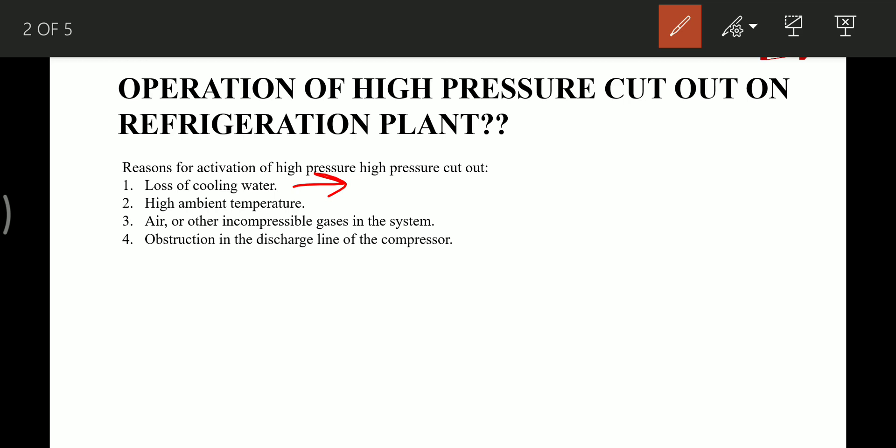The second reason is high ambient temperature. This point does not directly affect the system but indirectly. In case the main engine is running at full load or full RPM and the ambient temperatures are very high, the seawater is not able to cool the central cooling freshwater system and the central cooling freshwater temperature is not maintained. In that case, this high ambient temperature leads to high pressure cutout activation.